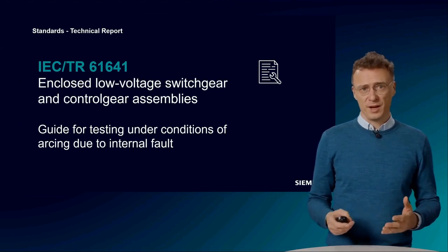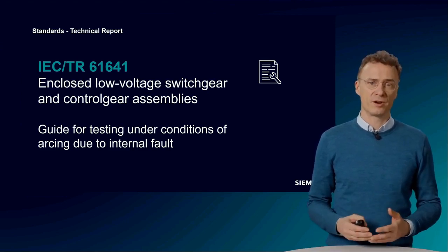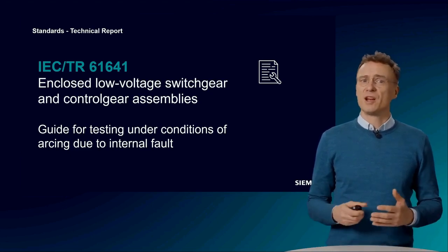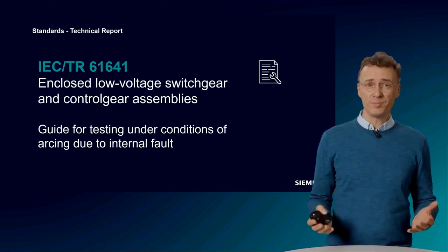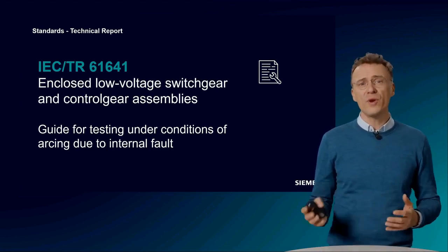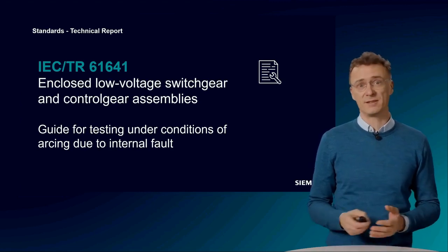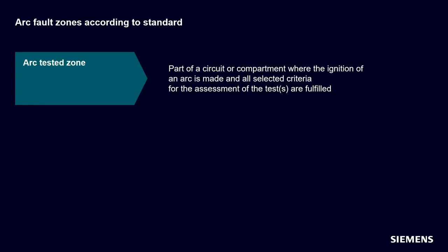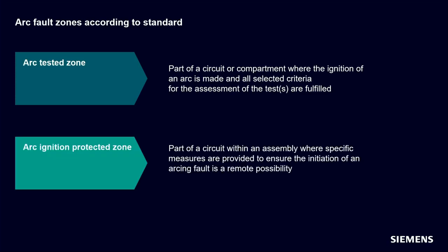The test parameters include voltage, currents, and the burning time of the arc, as well as who has access to the assembly — unrestricted access (everyone) or restricted access (only authorized personnel). The proof of arc fault protection can be carried out in two different ways: by testing, resulting in an arc-tested zone, or by taking appropriate measures that make the occurrence of an arc fault unlikely, resulting in an arc-protected zone — achieved, for example, by insulating conductors. In a switchboard, you will usually find a combination of both.